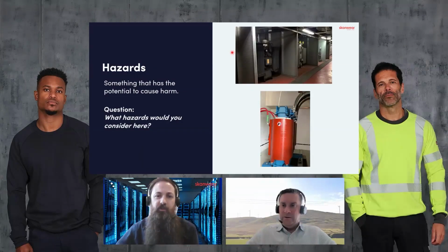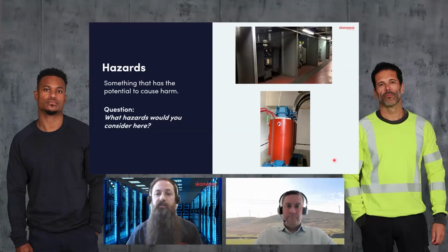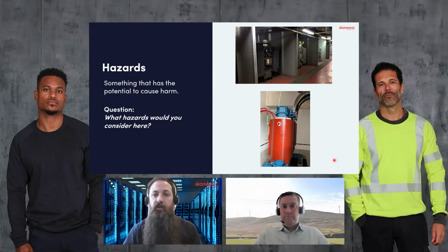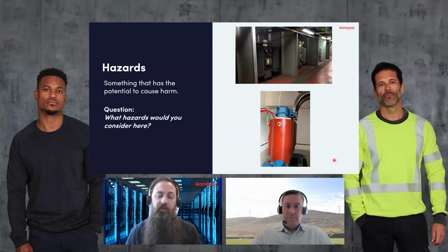Yeah, 100% exposed conductor, and a lot of the time access as well. With cast resin exposed conductors, a lot of the time they're interlocked with the ground switch or earth switch for the circuit breaker feeder for the transformer. So once you've got that in circuit earth or ground, you can remove the key, which then opens up that compartment. In this case it doesn't - there's just a plastic barrier across the front. So again, safety distances, massive one there, Joe. Thanks for that, definitely a good point.